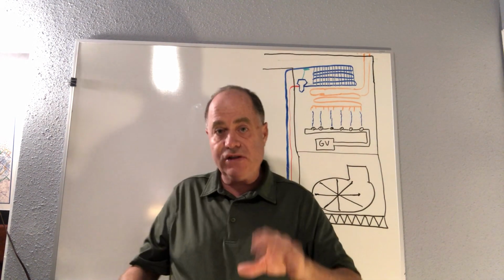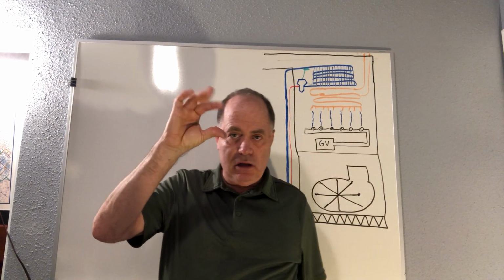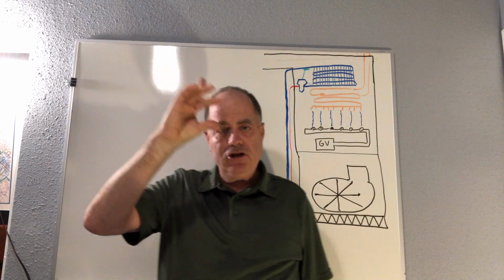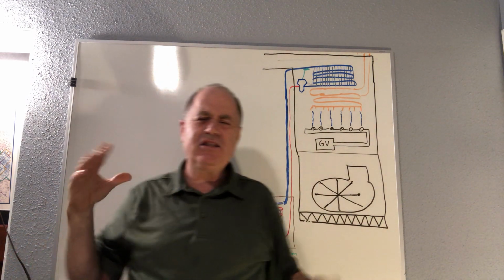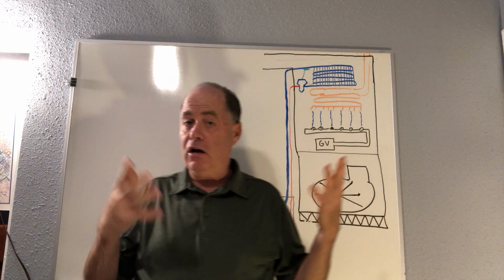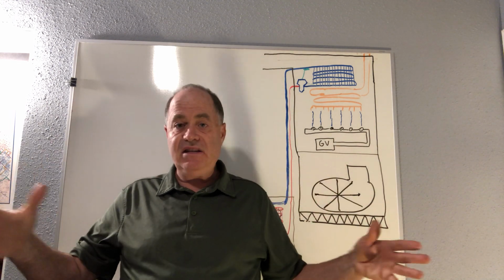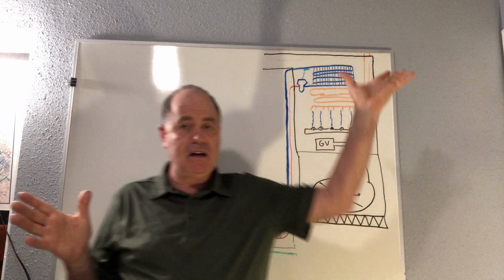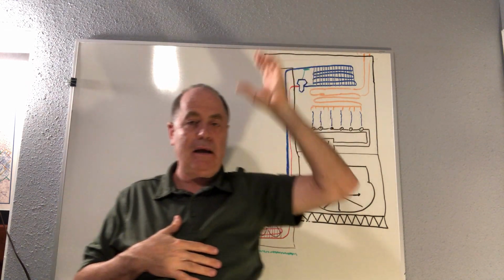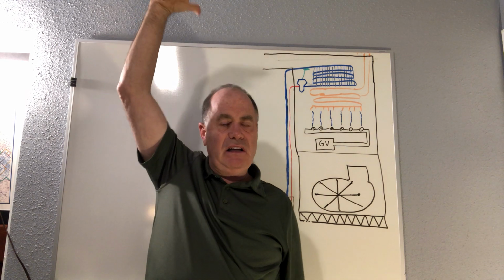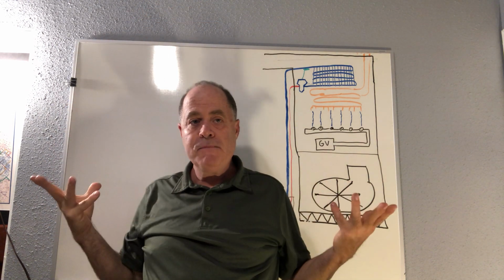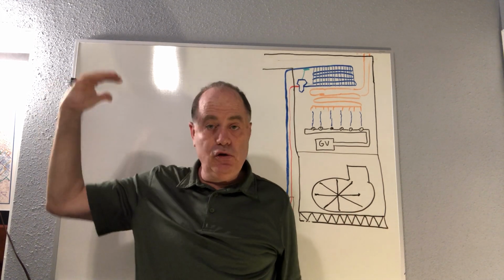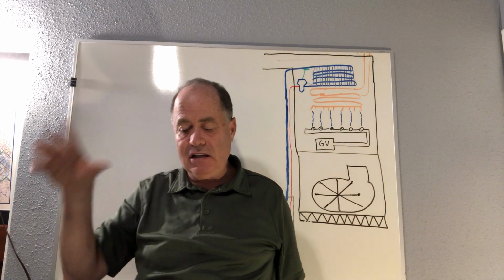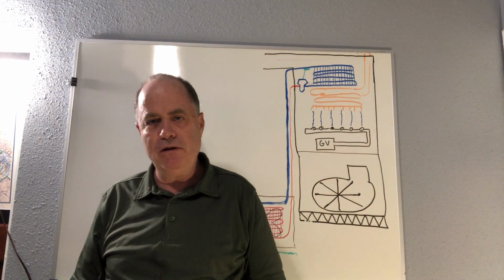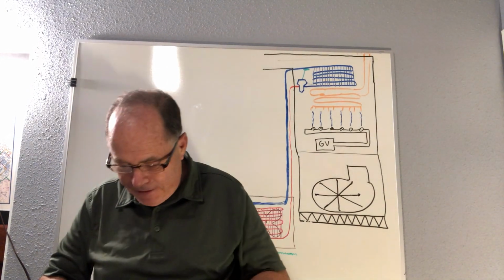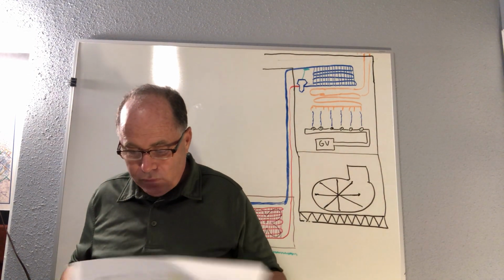Okay, again, unit heaters are mounted up against the ceiling. There may be a small clearance of about 6 inches, or depending on design, maybe only 2 inches if the manufacturer states that. And again, that's non-residential, more for like an automotive garage or a gymnasium or something like that. And then again, people don't like them because cosmetically you have something just hanging from the ceiling, which, especially if you have like 10-foot or higher ceilings, to me it's kind of interesting, because then you're actually saving space, and you're not losing any usable space, but people cosmetically don't like to see units. To me, it's the most beautiful thing in the world. Okay, now, all right, so that's the unit heater.